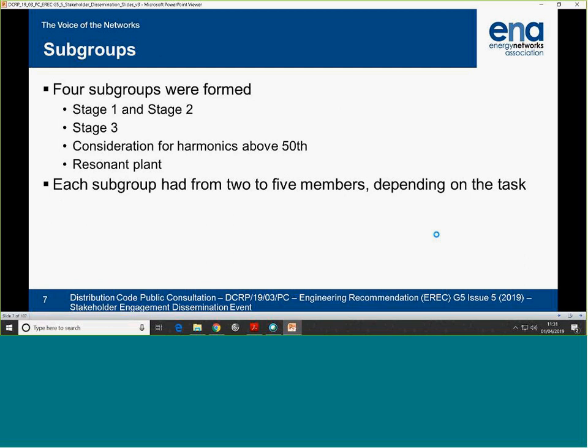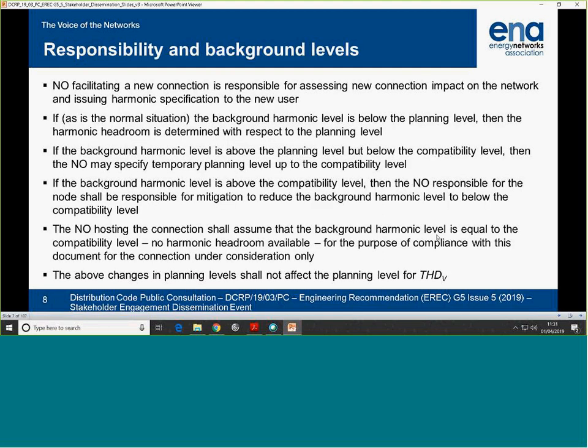Subgroups were formed: stage 1 and stage 2 subgroup, stage 3 subgroup, and conditions above 50th. So we gave that task to a subgroup to specifically look at that. Resonant plant: I'm sure you've heard about at MV and LV, people's capacitors damaged because of harmonics. So we thought, because there was no guidance in G5/4, perhaps we need to put something there so that they can be looked at and assessed before they're connected. We had a larger subgroup and a smaller subgroup depending on the cost.